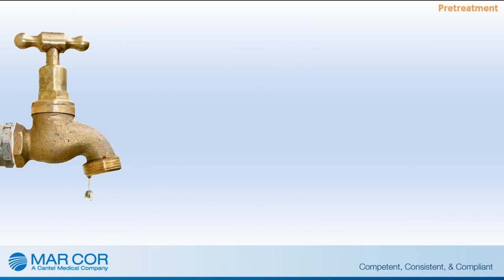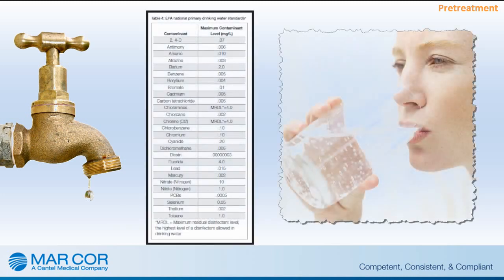Incoming feed water contains solutes that exceed the safe levels needed for making dialysate. Although these levels of solutes may be safe for drinking water, they are considered contaminants if above the safe levels for the production used for hemodialysis.